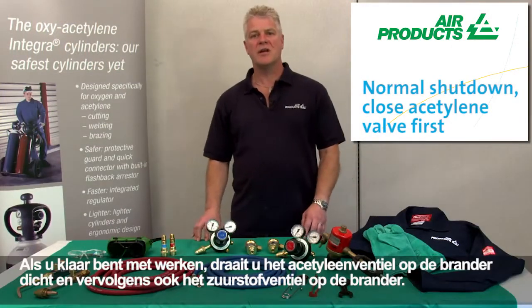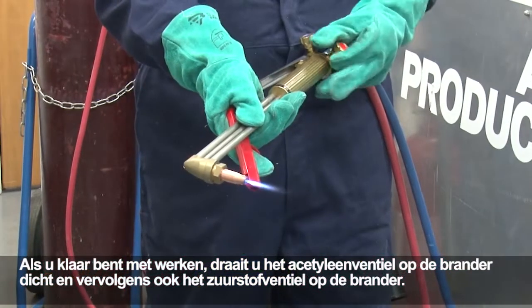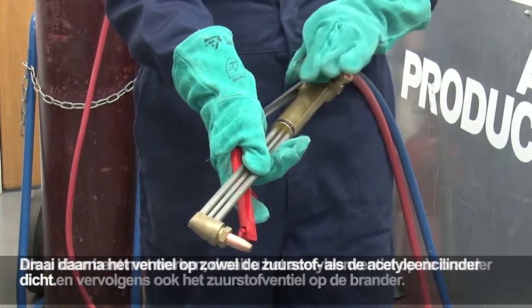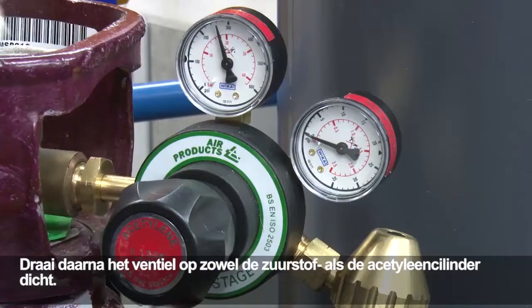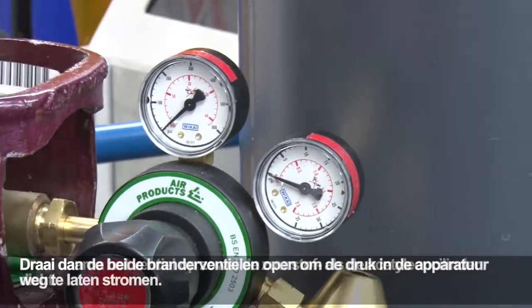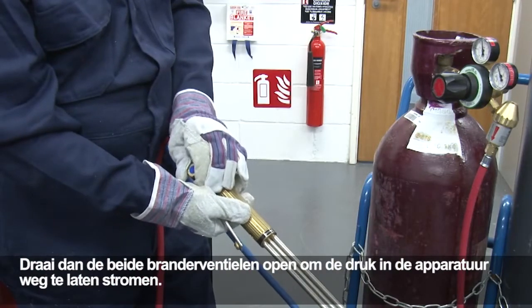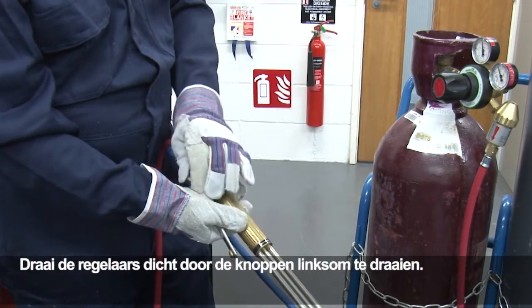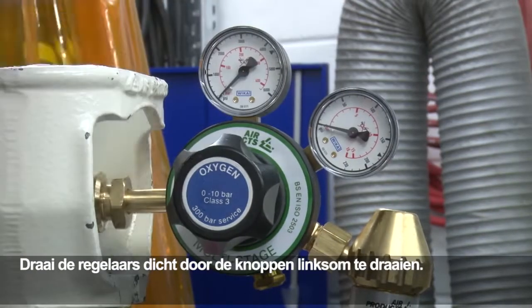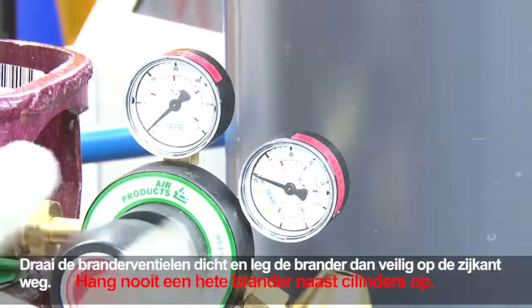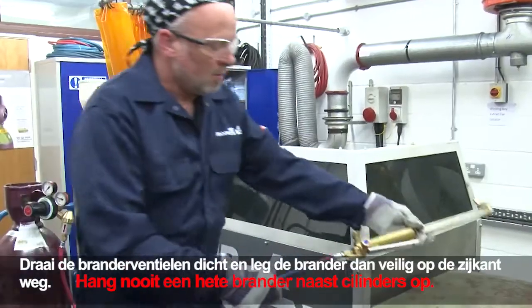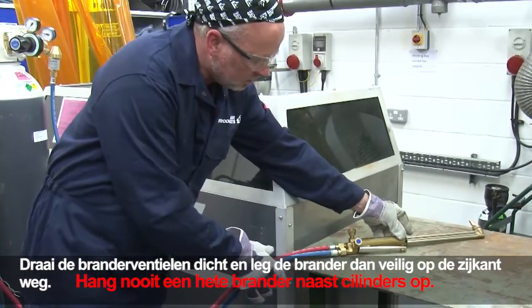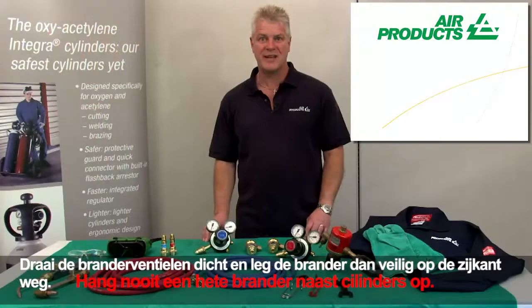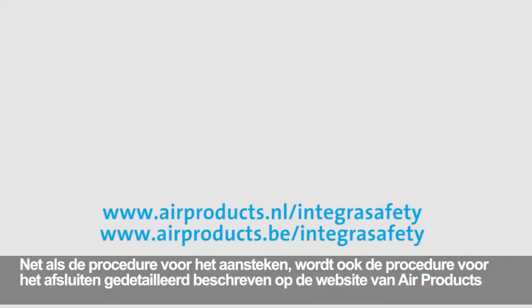When you've finished working, close the acetylene valve on the torch and then close the oxygen valve on the torch. Next, close both the oxygen and acetylene cylinder valves. Then open both torch valves to vent the pressure in the equipment. Close the regulators by winding the pressure adjusting knobs anti-clockwise. Close the torch valves, then safely place the torch to one side. Don't ever hang a hot torch next to any cylinders. As with the lighting up procedure, the closing down procedure is described in detail on the Air Products website.